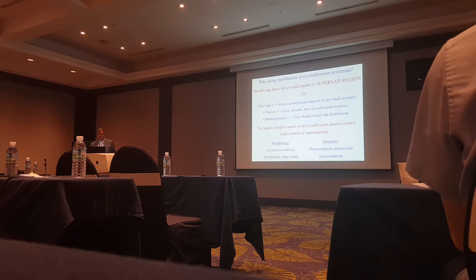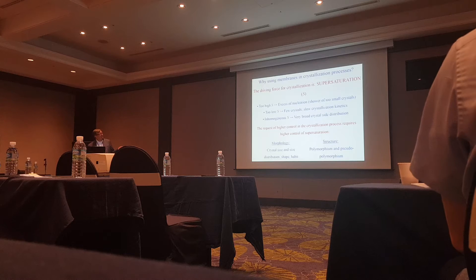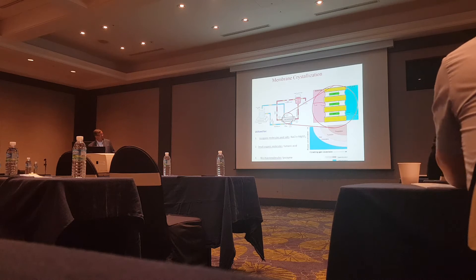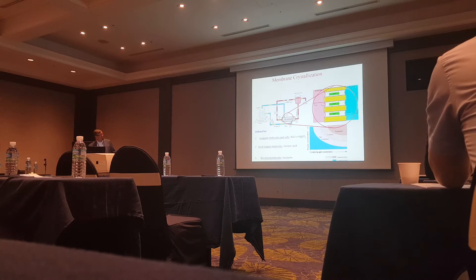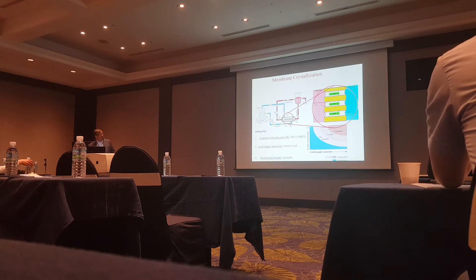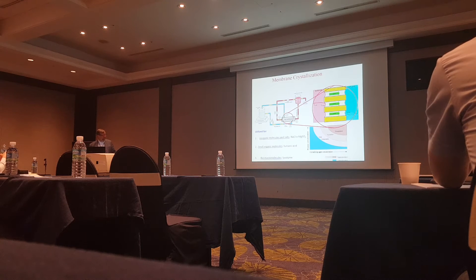That's what we are doing today — you can find most of the published data in the literature. The driving force in crystallization is just the difference in vapor pressure across the membrane. It's nothing more than a traditional membrane distillation loop where you concentrate the brine as much as possible, but if you want to produce crystals, you must also be able to continuously separate the crystals from the loop, so you don't introduce too much mass resistance into the system.